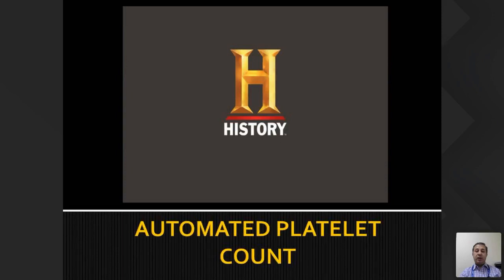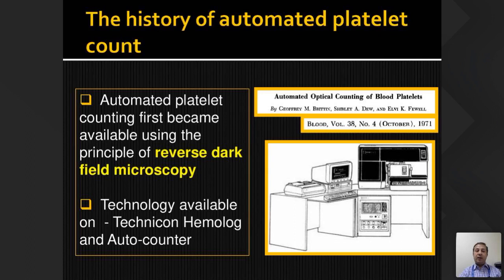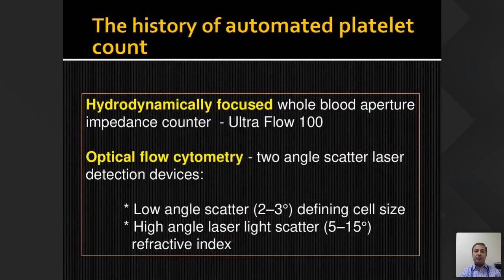The first automated platelet counting became available as reverse dark-field microscopy many years back, using technologies like Technicon, Hematology, and Automate cell counting analyzers. As hydrodynamically focused systems came up, whole blood impedance counting became more prevalent and platelet counting became more reliable, using triplicate counting and fitting curves. Eventually lasers came into picture in automated hematology analyzers, enabling optical flow cytometry-based cell counting using two-angle light scatter devices — low angle and high angle scatter — looking at cell size and refractive index.